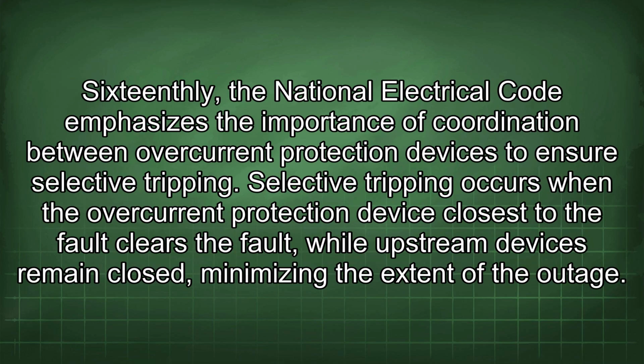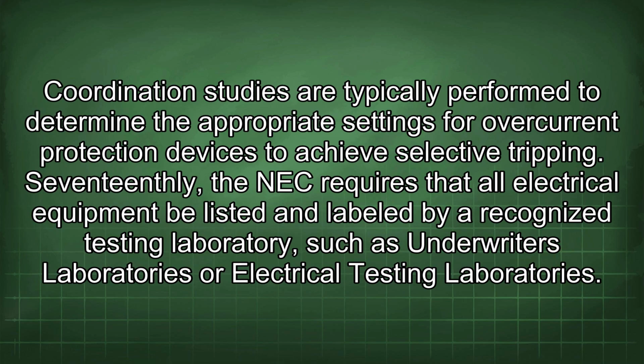16thly, the National Electrical Code emphasizes the importance of coordination between overcurrent protection devices to ensure selective tripping. Selective tripping occurs when the overcurrent protection device closest to the fault clears the fault, while upstream devices remain closed, minimizing the extent of the outage. Coordination studies are typically performed to determine the appropriate settings for overcurrent protection devices to achieve selective tripping.